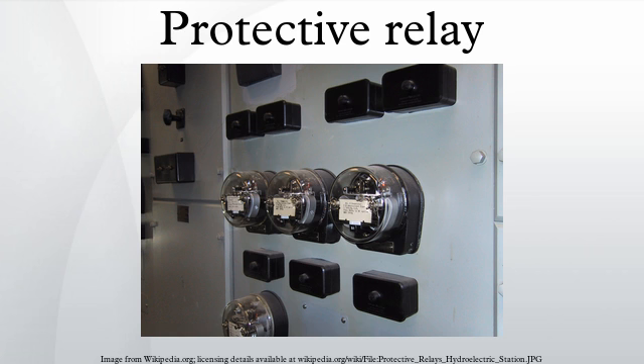As supply grids are generally well interconnected, the fault in the previous example will be fed from both ends of the power line. The relay at substation A will see a massive increase in current and will continue to export. Substation B will also see a massive increase in current, however it will now start to export as well. In turn, the protection relay will see the currents traveling in opposite directions, and instead of cancelling each other out to give a summation of zero, it will see a large value of current. The relays will trip the associated circuit breakers. This type of protection is called unit protection, as it only protects what is between the current transformers.